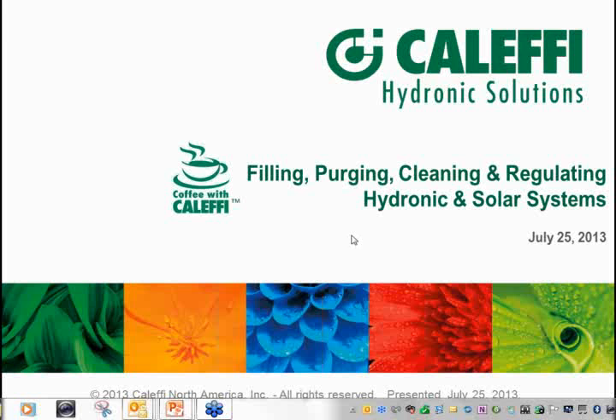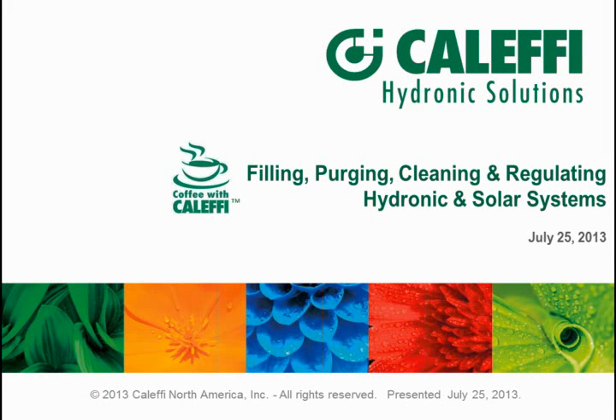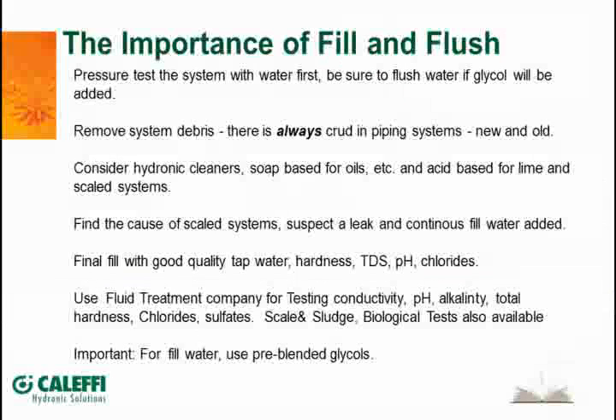And why that's more critical now than it was in the past is, back in the early days when we were putting in cast iron boilers, if you ever broke apart a cast iron boiler to take it out of a basement or something like that, you'd notice the cast iron could have been up to a quarter inch thick in spots. So you had a lot of metal there to corrode away and still not have a leak in the system.